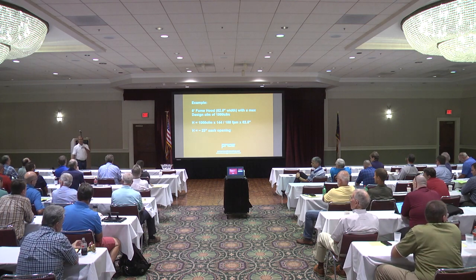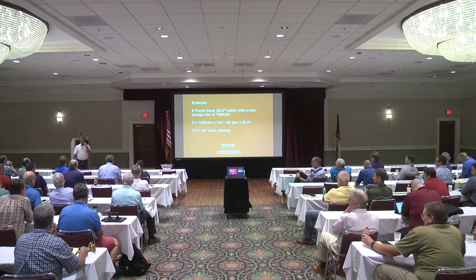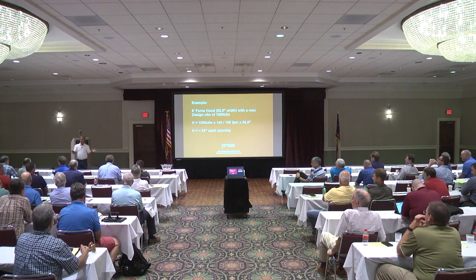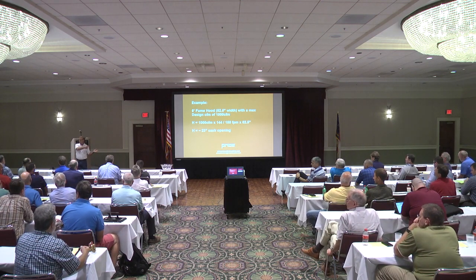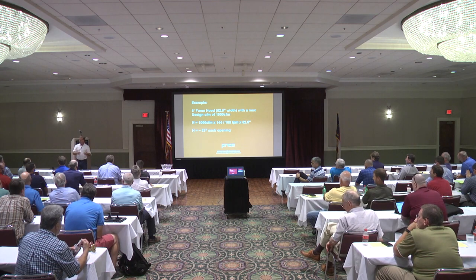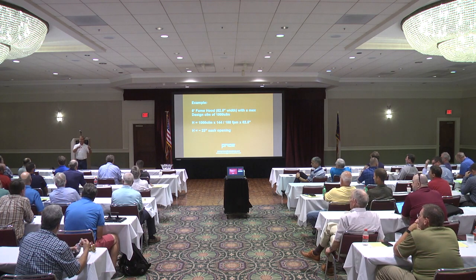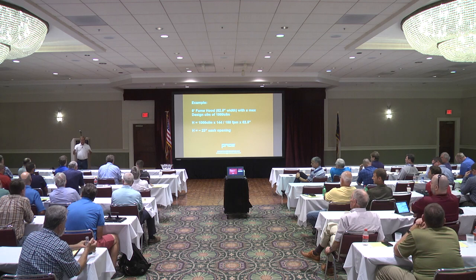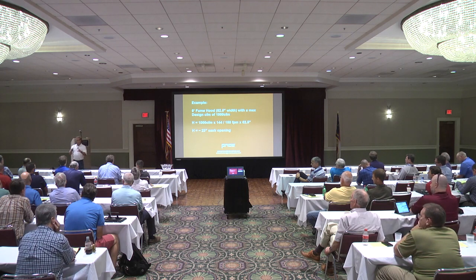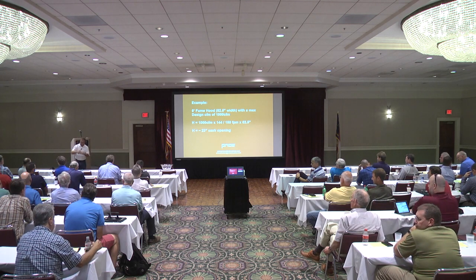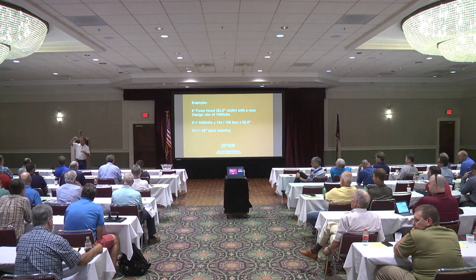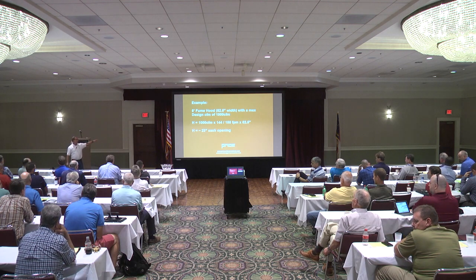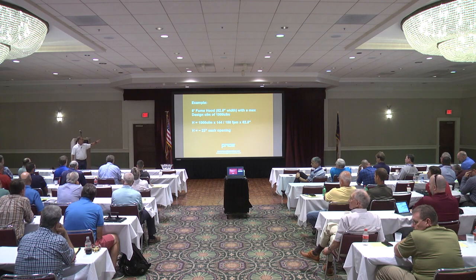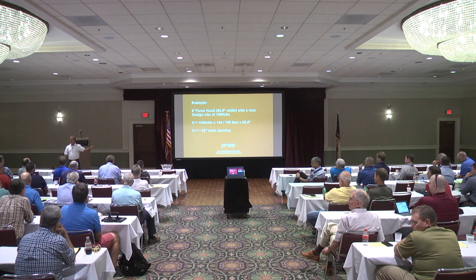Well, if you walked up to a fume hood and said, I need to test this fume hood for 1,000 CFM because that's the design, and it's a VAV fume hood, and the VAV fume hood's been set up per the project documents for 100 feet per minute, that's its design point from closed, or from minimum to maximum. Well, if you only go to 18 inches, you're only going to see 100 feet per minute. And 18 times 62.5 divided by 144 times 100 is 781.25 CFM, not 1,000.